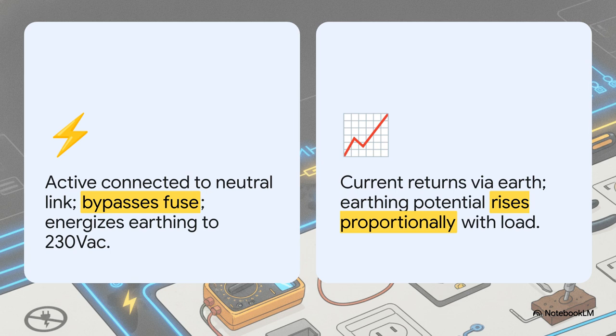So we're looking at two distinct yet equally dangerous faults here. First, a reverse polarity service. This is where the active supply is connected directly to the neutral link. It completely bypasses the service fuse and instantly energizes the whole earthing system to about 230 volts AC. Boom! Immediate lethal shock hazard.